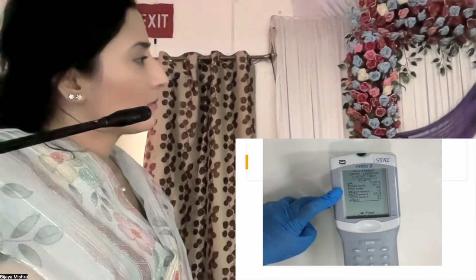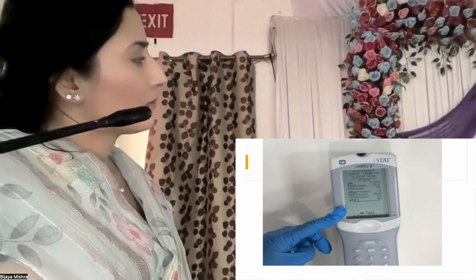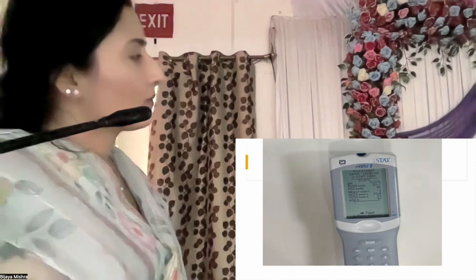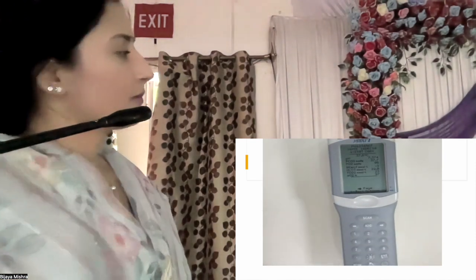And the parameters which are measured is pH, PCO2, PO2, base excess, HCO3, oxygen saturation. The analyzer then stores this record, and you will be able to retrieve it manually when required. So as simple as 20 seconds and the patient's ABG reports are made available. And we could see here.